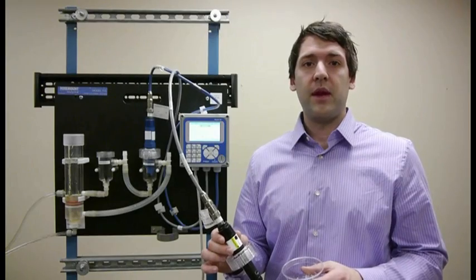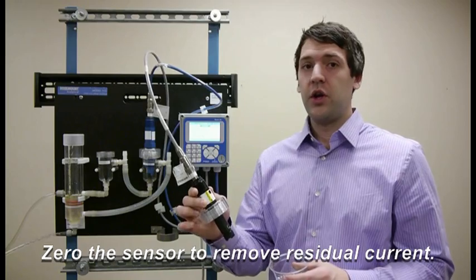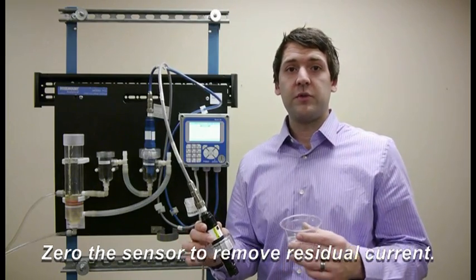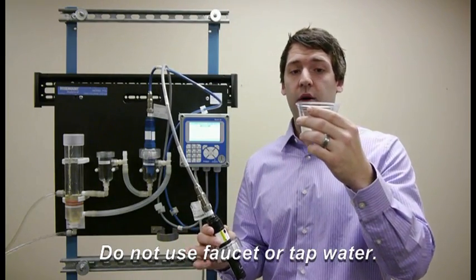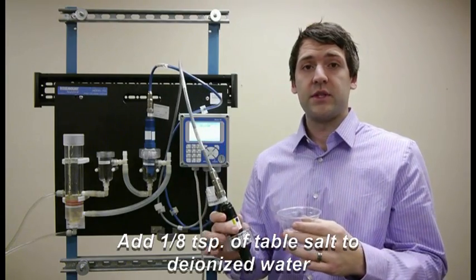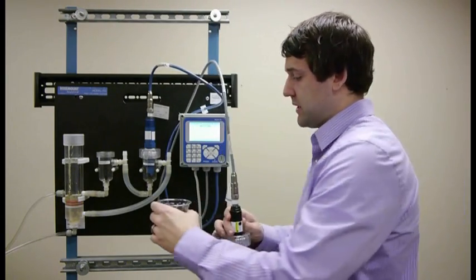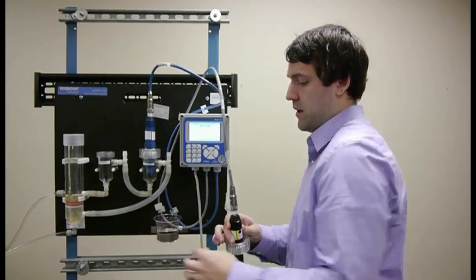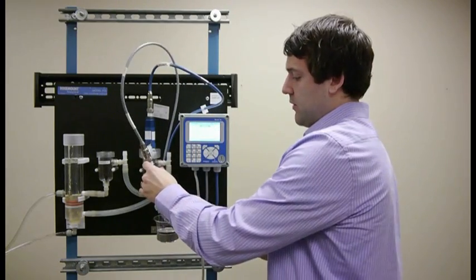So after you've replaced the membrane head and the fill solution in the sensor, you're going to need to zero the sensor. You do this by taking a glass of non-chlorinated water and throwing a little salt in there so it's conductive enough for the reading. Place it in the cup holder, and then take the sensor and place it in the water.